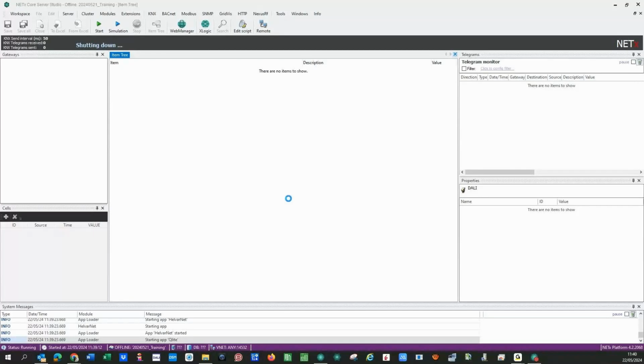So you will see this first approach is that we get a lot of information structured. We have in a structured way all this information in LaMPS. So if you want, one of the items is just if you have any problem with DALI in the installation. So with just monitoring this item, you will get, for example, an alarm, or you will get a message. We will see how to send an email or a Telegram pop-up message. Very easy, but it's possible to get this information, including the emergency devices and so on.